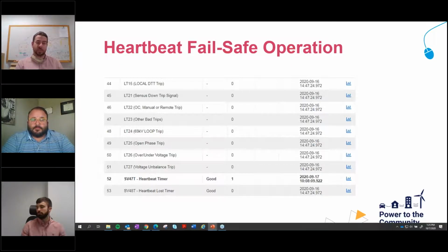When we start up a new site, we have to give it a little quick kickstart, and we start up a timer, and that's point number 52 there. So we start the timer and set the point to 1. In 5 minutes, that point will change from 1 to a 0. Sensus is constantly watching the device, and it'll see that point change to 0. We have a control action that's set up, and when it sees it set to 0, it sends a pulse, resets that point back to 1. And that occurs every 5 minutes, every day, and it's been doing it since the system went online in November. Every 5 minutes, constantly sending a pulse.